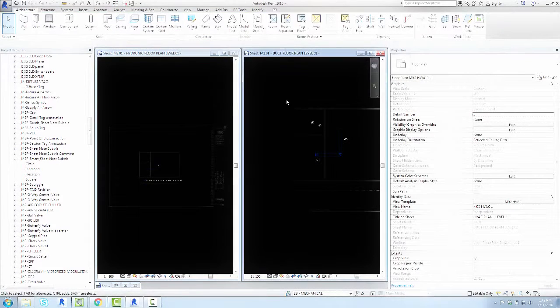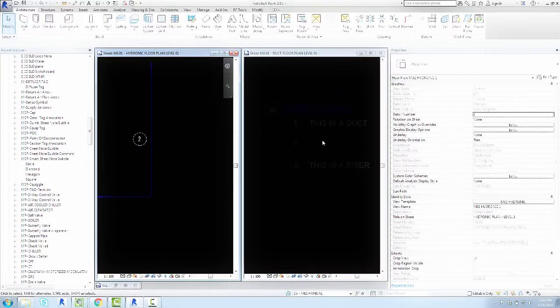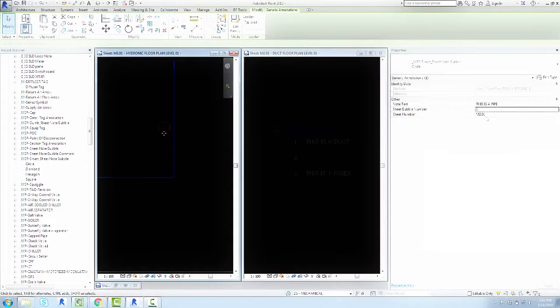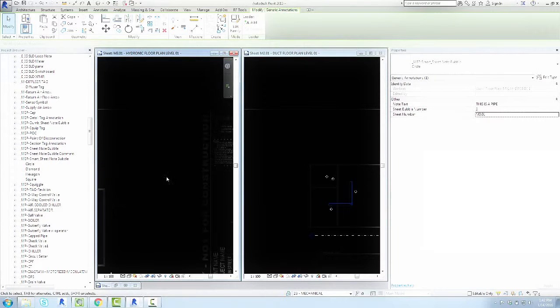And I'm like, well, why isn't it showing up here? That's super messed up. Well, the reason is because the sheet number is M201. It's a sheet M301. Let's look back at M201. You'll notice two is blank again. That's because this schedule isn't reading sheet note bubbles from just this view. It's reading sheet note bubbles anywhere. And that's why we need this parameter that says sheet number M201. It tells the sheet note schedule which of these guys to look up. So that's fine. All I do is change this guy to M301, and then my M201 schedule fixes itself because now it's just reading these two guys. And now over here, this one is reading it correctly.